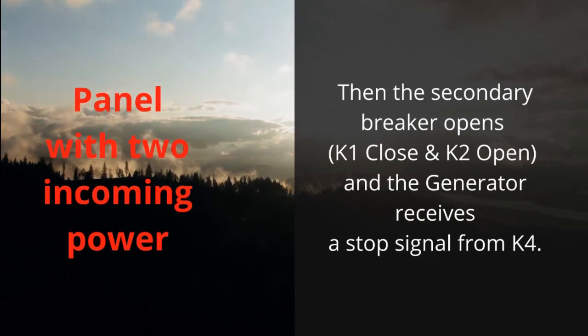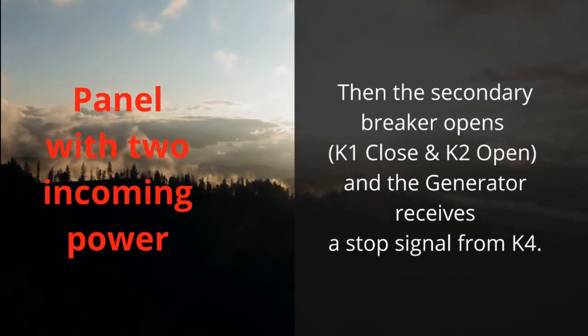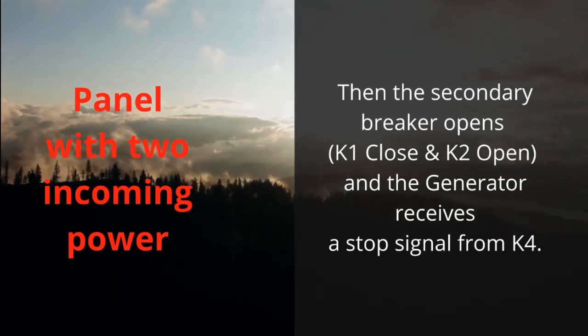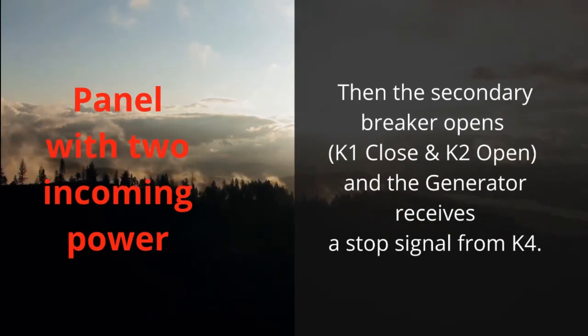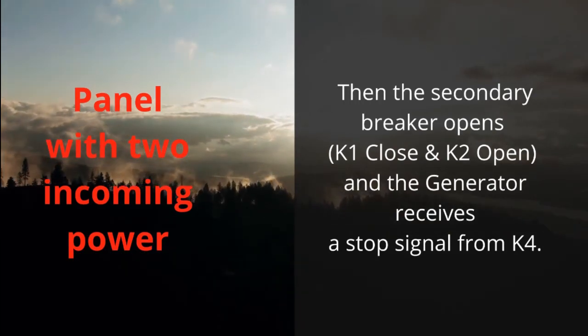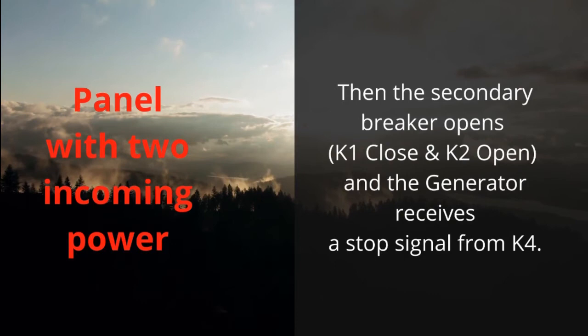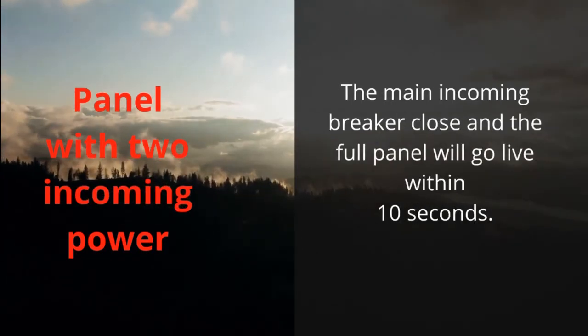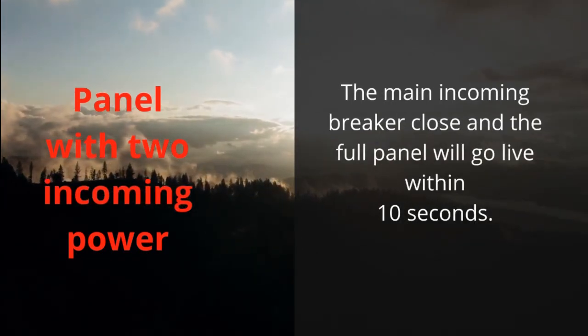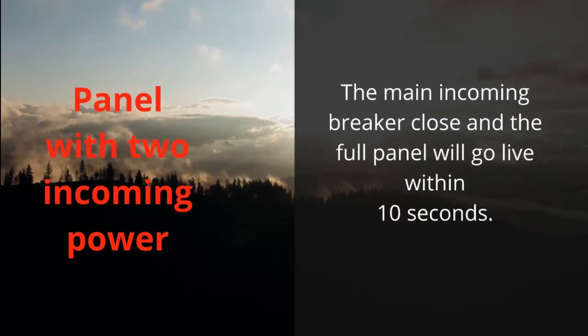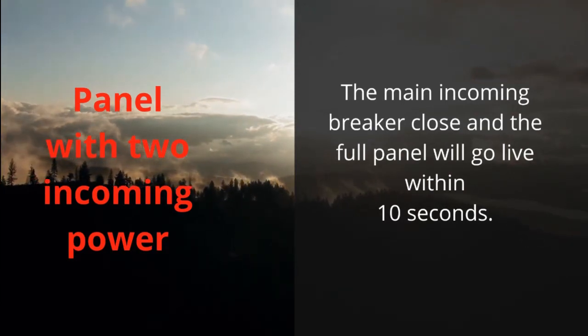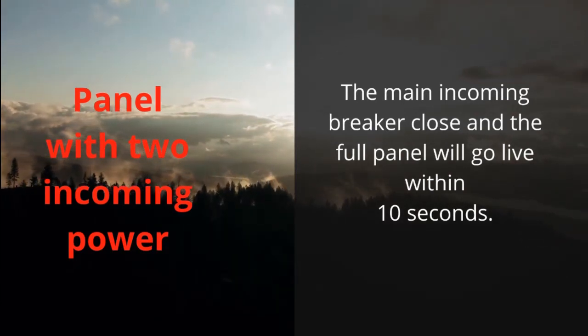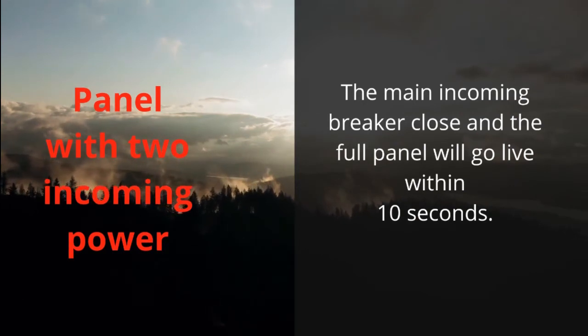Then the secondary breaker opens and the generator receives a stop signal from K4. The incoming breaker closes and the full panel will go live within 10 seconds.